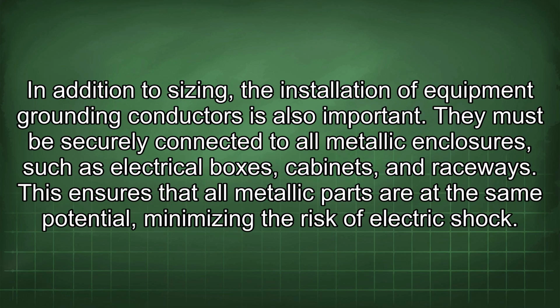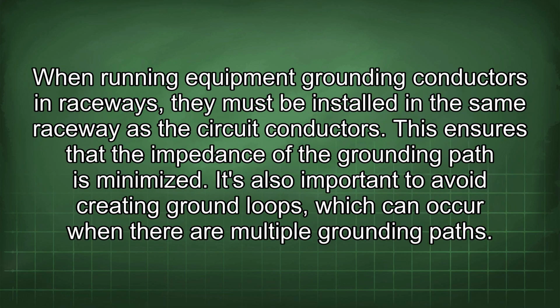In addition to sizing, the installation of equipment grounding conductors is also important. They must be securely connected to all metallic enclosures, such as electrical boxes, cabinets, and raceways. This ensures that all metallic parts are at the same potential, minimizing the risk of electric shock. When running equipment grounding conductors in raceways, they must be installed in the same raceway as the circuit conductors. This ensures that the impedance of the grounding path is minimized.